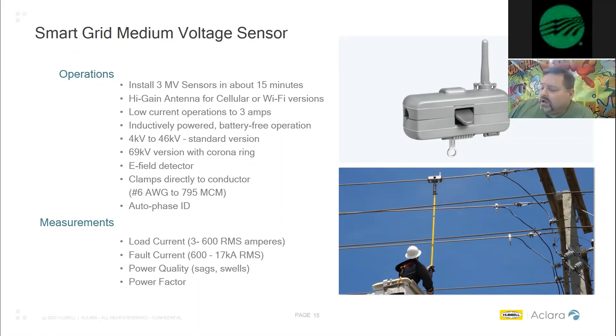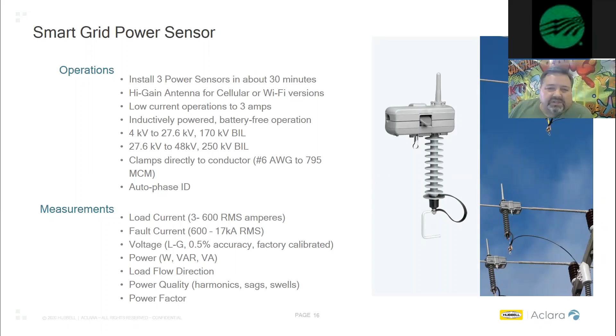However, its big brother is called the power sensor, and frankly this is the one that most everybody is putting in. You have a reference to ground or neutral there through the power resistor, and this will give you the same as the MV sensor plus voltage with 0.5% accuracy, plus real power, load flow direction, and power quality with harmonics, sags and swells, waveforms, and power factor. This is the primary sensor that John has been selling to most of his customers.